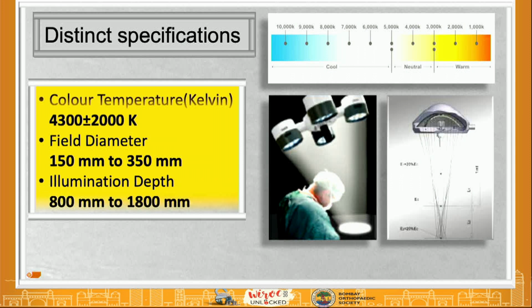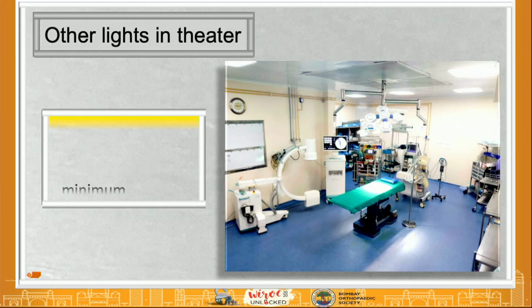3 distinct specifications which I like to mention is about the color temperature Kelvin, which is from the darkest red to the darkest blue. So you can have as natural light as possible, and the diameter of that field should be from 15 to 35 centimeter. And the illumination depth, like you are doing a TKR and the knee is flat, so knee comes up near the right and then it goes down. That way you should have some 80 centimeter to 180 centimeter type of a range where the focus should be there. So you have to go into technical detail of this.